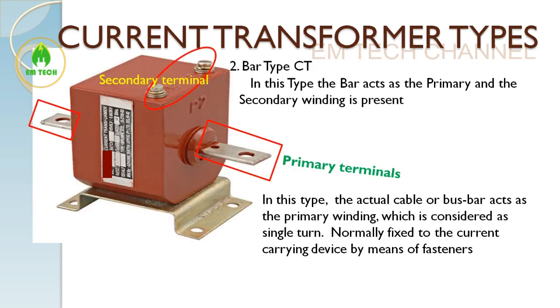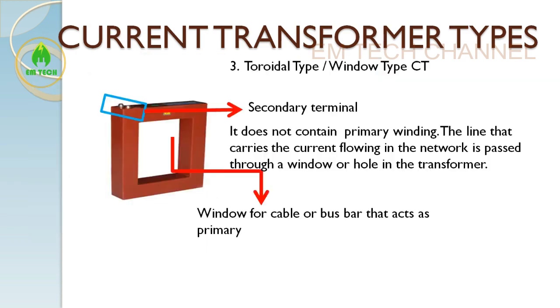In the third type, the actual cable or bus bar acts as a primary winding, considered as a single turn, and is normally fixed to the carrying device by fastening. This is called the toroidal or window type current transformer — this is what we are going to explore today. Unlike the bar type and wound type CT, it does not have a primary winding. Instead, the cable for which we want to measure current passes through this hole, acting as the primary.